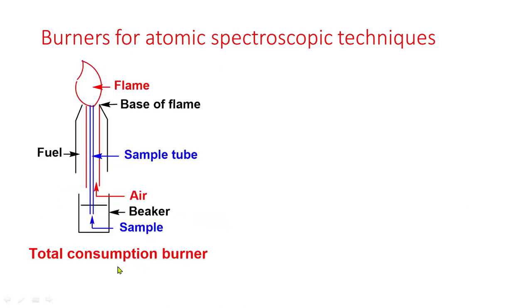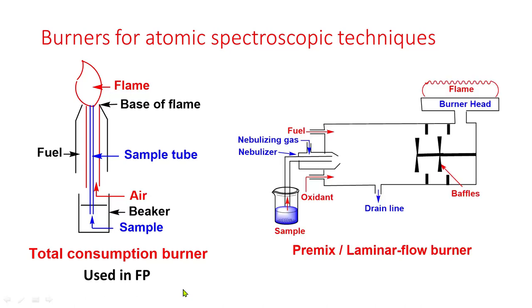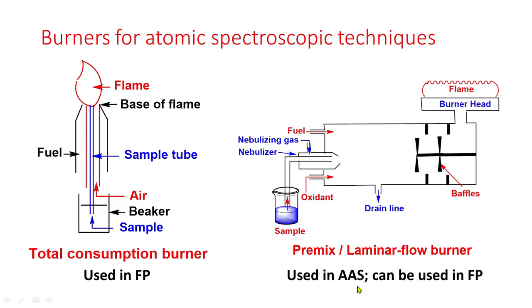This diagram shows the total consumption burner, which is used in flame photometry. This diagram shows the premix or laminar flow burner, which is used in atomic absorption spectrophotometry and can also be used in flame photometry.